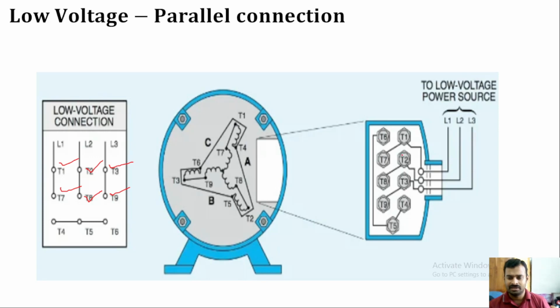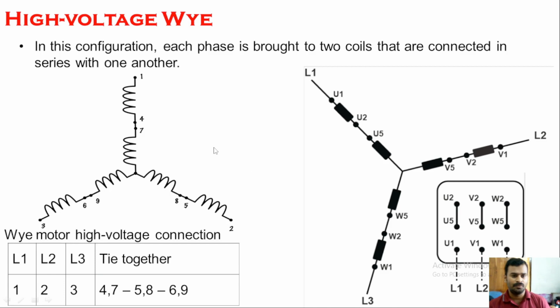When we make the connection like this, it will give us a low voltage star connected motor. And if you want to make that same motor a high voltage star connection, we are going to make the wiring in a different way. Here we are going to connect L1 with terminal 1, here L2, and here L3, and we are going to short terminals 6 and 9, 8 and 5, 4 and 7. So that is what is given here.